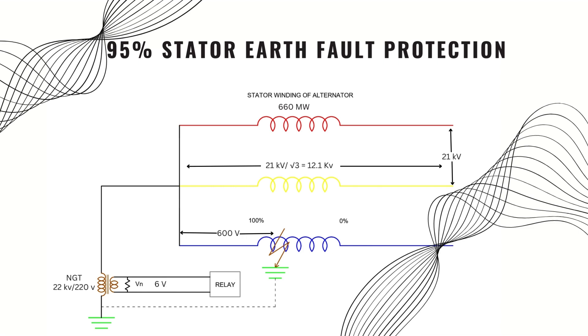The relay is set at this voltage and the time setting will be 1 second. That means if the VN becomes 6 volts for 1 second, then the relay will trip the generator.